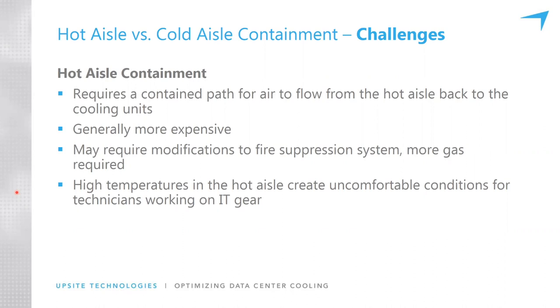And high temperatures in the hot aisle really get exaggerated. This can be mitigated by temporarily placing supply tiles in the hot aisle where somebody is working, and other means of limiting the time. I know this is an issue that very often comes up, of why people can't do hot aisle containment or why they won't do hot aisle containment very thoroughly. But these issues can be mitigated. I mean, people work in steel mills that are way worse environments than a hot aisle in a data center. So it can be addressed.